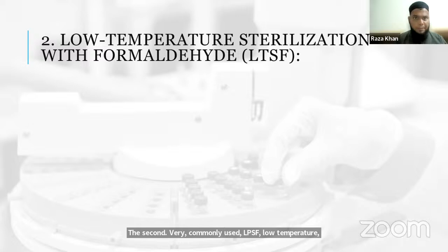The second very commonly used method is LTSF, low temperature sterilization with the help of formaldehyde. In LTSF technology, we use formaldehyde at a lower temperature for sterilization. Instruments are usually exposed to formaldehyde vapor in a sealed chamber. This is an effective, broad spectrum pathogen destroying mechanism, suitable for heat sensitive materials. It also has some limitations: if there is poor ventilation, then formaldehyde can create toxicity. In this method, validation of sterilization for efficacy is very essential.